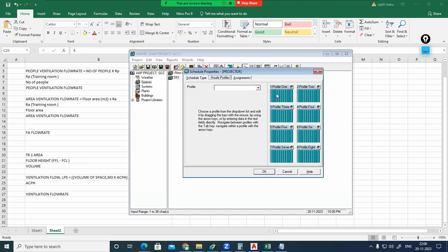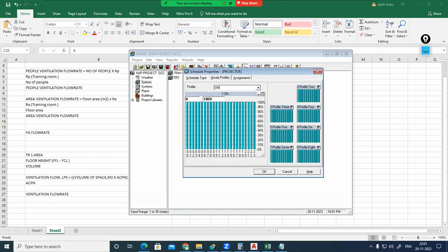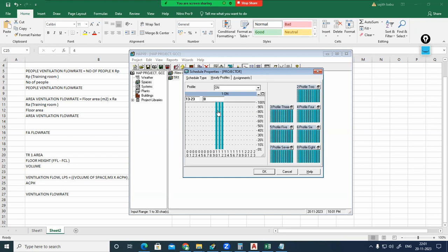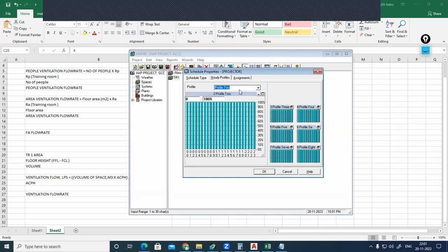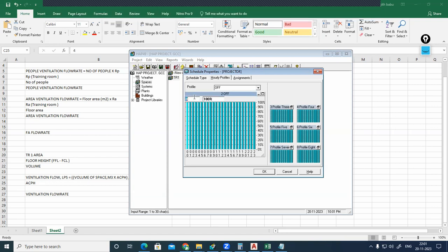Projector. Go to hourly profile. Profile number one, the projector is on. There is no need for an allowance, because it doesn't mean that 50% of the projector will be used before 10 and 50% after 12. No, 10 to 12 will be 100%. All the other times, 0 to 9, will be 0. 13 to 23 will be 0. 10 a.m. to 12 will be on. Profile number 2, the projector is off. 0 to 23, no one will be using that. That is 0%.